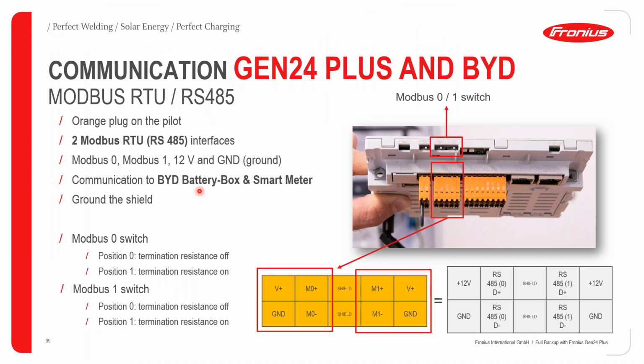Ensure that the switches are on position 1, depending on the modbus you want to use for any respective function. Because if it is not, you wouldn't have any communication with either the BYD battery box or the smart meter. Integrated in this switch is a 120 ohms resistor. So this actually completes the communication connection between the pilot, which is a communication gateway for the inverter, and either the battery box or the smart meter. So ensure that this switch is on position 1.